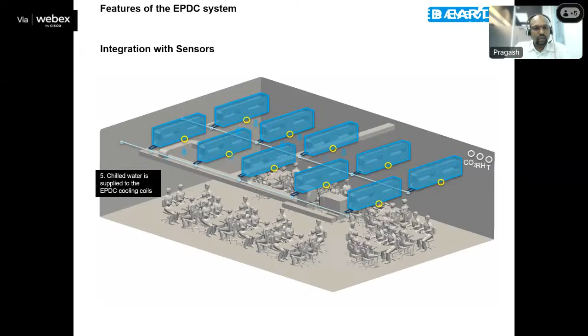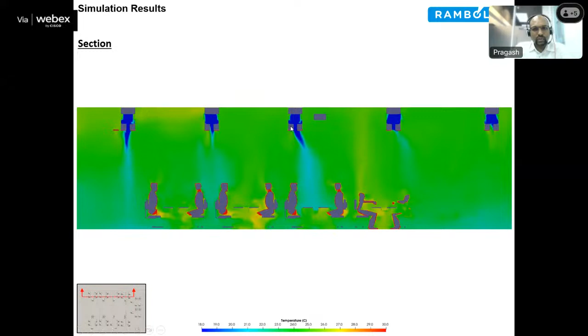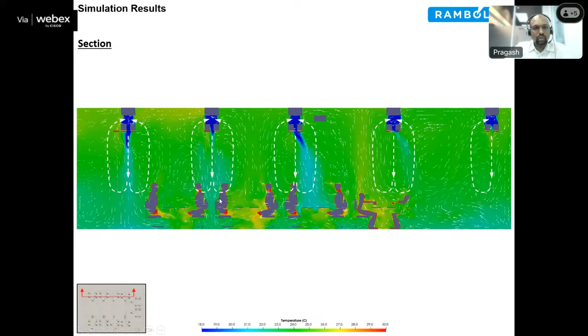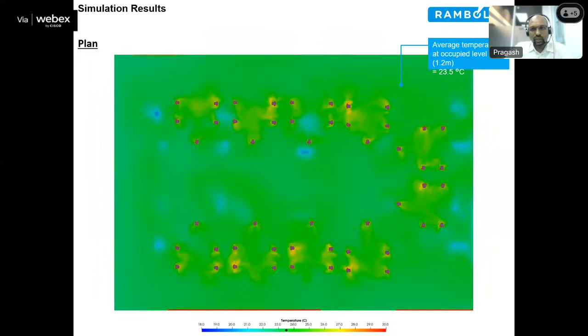So here you can see the simulation result. The dark blue color means very cold air, about 16 to 18 degrees. The air is directed down with this small down duct on both sides, down to the occupied zone. You can see the arrows showing how the air moves passively according to the heat load generated. Then this is the temperature in the plan view, achieving about 24 degrees. That's our design temperature at the occupied zone.